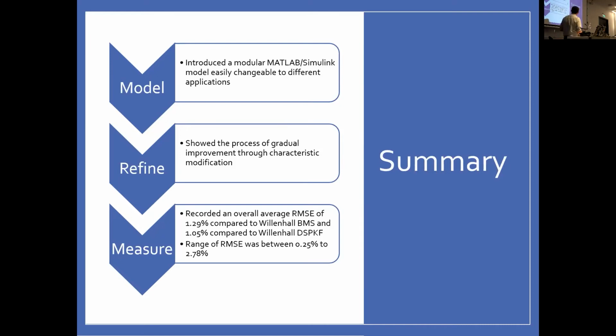We measured how accurate we made it with a recorded overall average RMSE of 1.29% compared to the BMS system and 1.05% compared to the DSPKF system - so on average about 1.15% out from the recorded value at the real world installation, which is within the realms of accuracy we want. It ranged between 0.25% and 2.78% in general, so certainly within 3% error, which we're very happy with, but there's obviously scope for improvement as we continue the incremental development of the model.